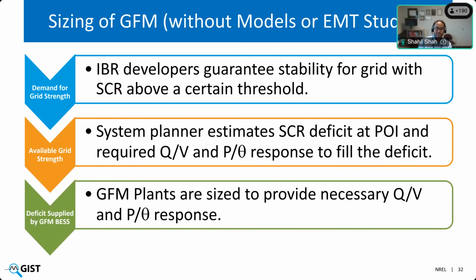objectives, which is just this slide, which talks about how we can size grid forming resources without models and EMT studies if we know this performance matrix. So if IBR developers guarantee stability for their IBRs for grid short circuit ratio above a particular threshold, and as a system planner, you would know what is the deficit, or what is the actual short circuit ratio where you are connecting those IBRs, and then calculate the deficit of IBRs. That can be met by grid forming plants by properly procuring the Q by V and P by theta response, or basically, in other words, procuring active and reactive power response.